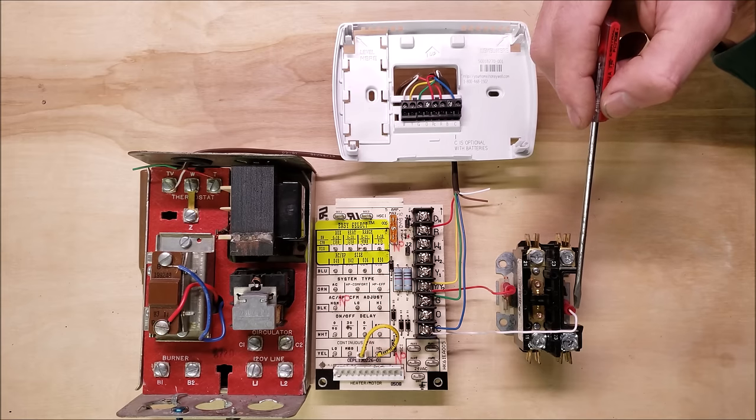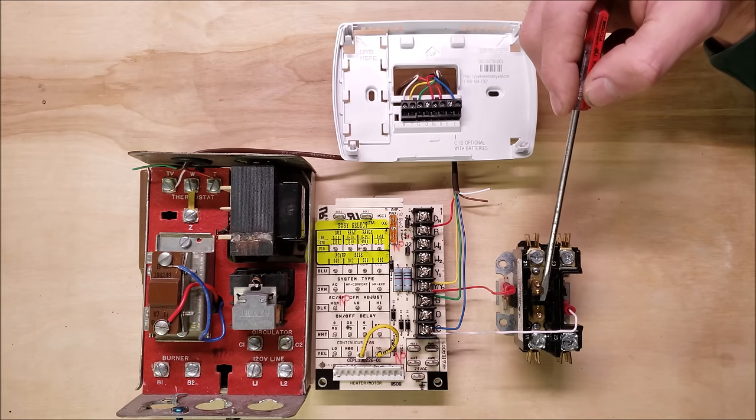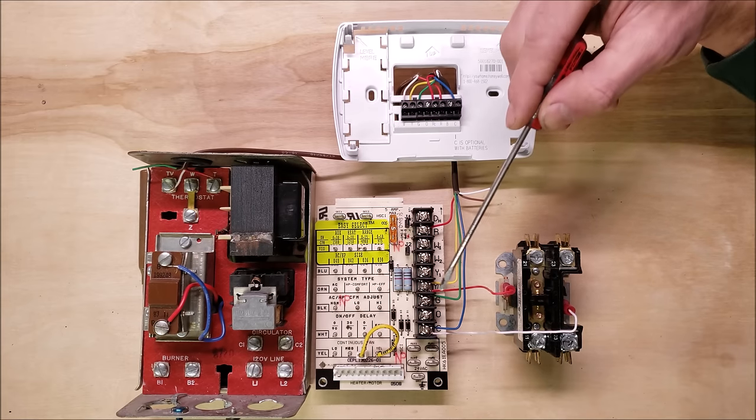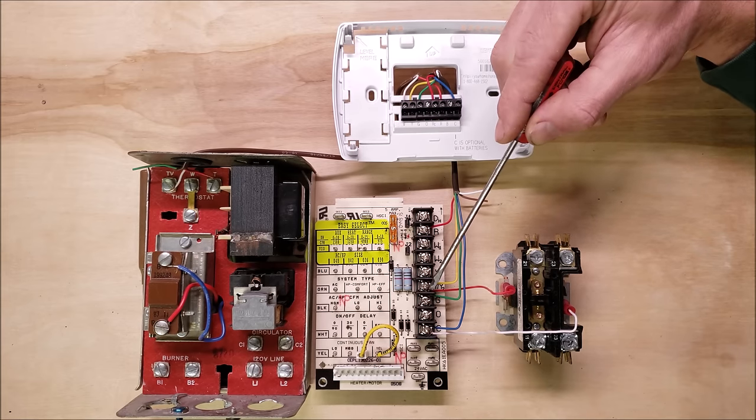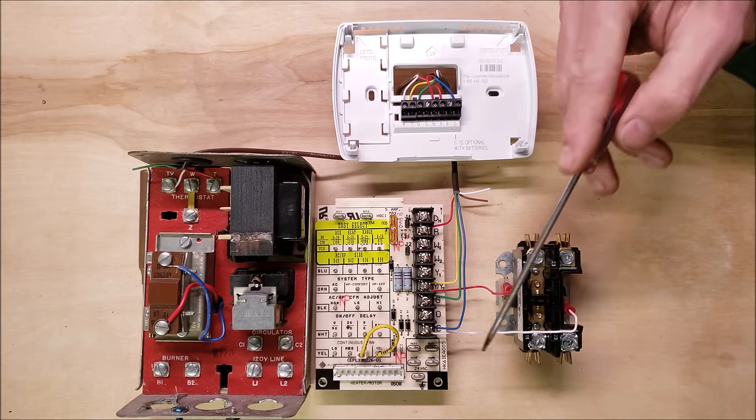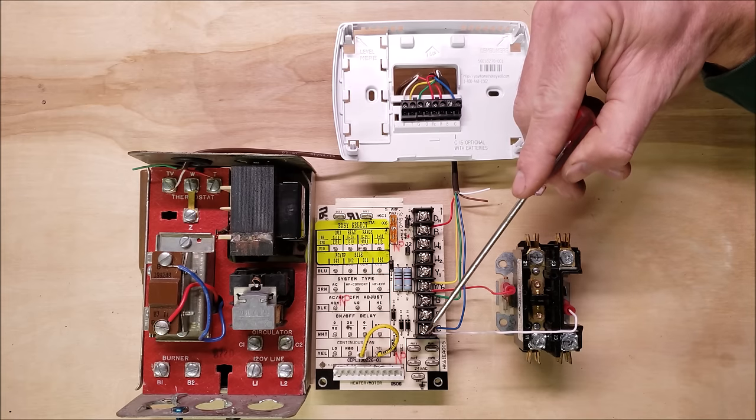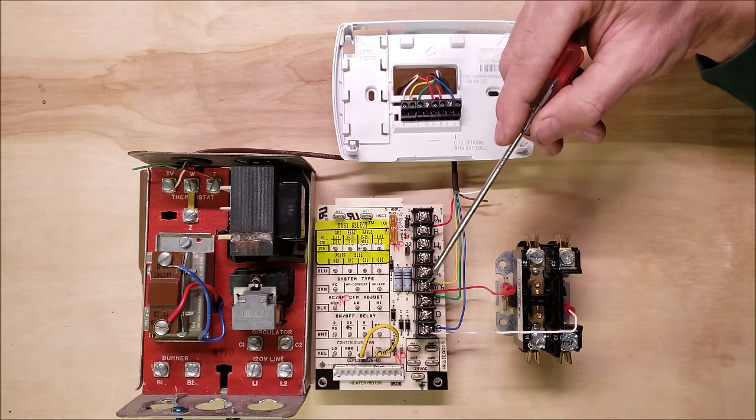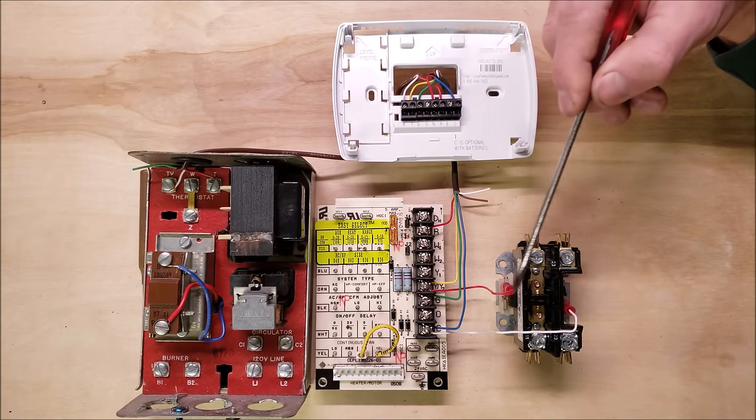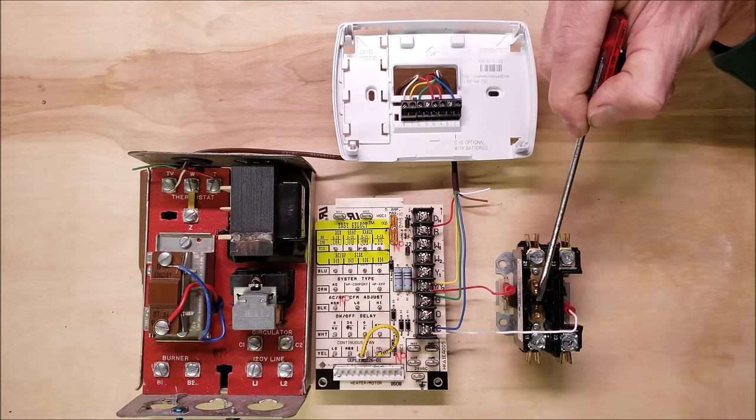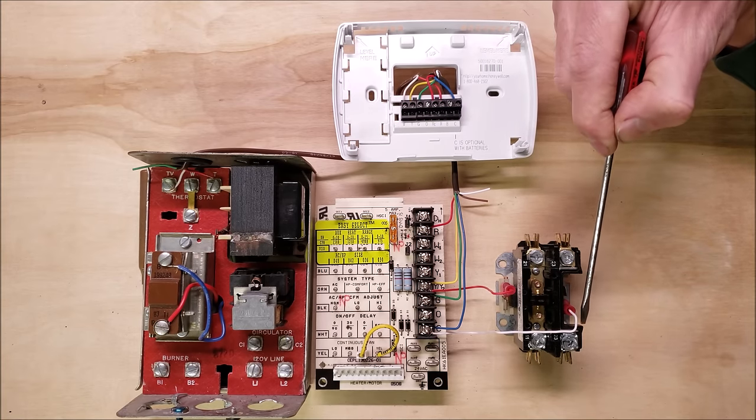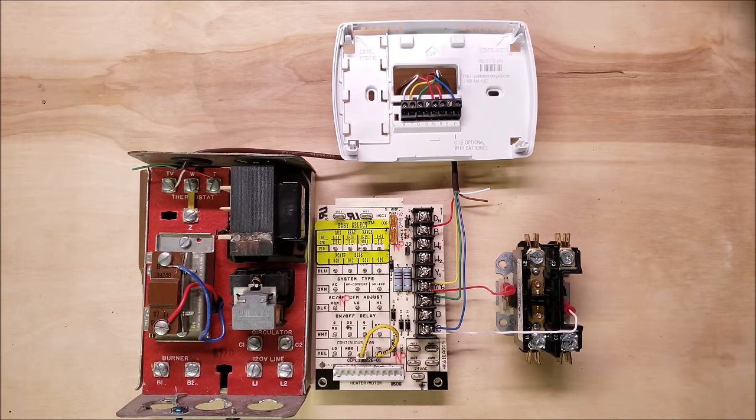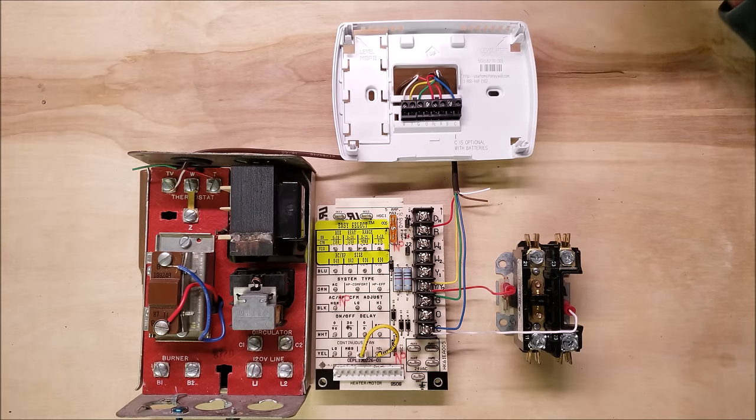You have a 24 volt coil here and it pulls this down anytime you have 24 volts on Y, and C is always your path back. So Y 24 volts is coming over to your contactor pulling in this contactor and coming back through the common to the common side of the transformer.